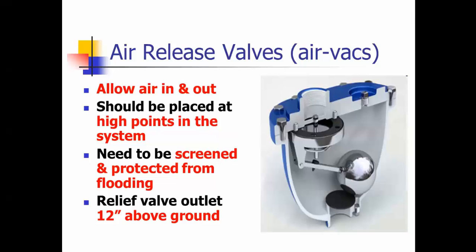On an air vac, that allows air in and out, and so you have your ball float here, and they should be placed at high points of the system. If you have a sudden draw, you want those at a high place so that air can get into the line and so that it doesn't collapse. They need to have a screen on them. It's a number 14 mesh screen. And in the wintertime, you ought to inspect those air vacs to make sure that they don't ice over, because if they ice over, they won't work. The relief valve outlet is about 12 inches above the ground.